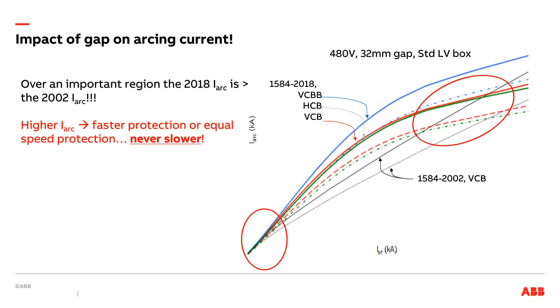I'm not addressing that here. I'm trying to address your more typical industrial commercial systems where your gear is rated 65 kA or below, and you're dealing with those more reasonable typical currents. In that IBF range, arcing current typically in the new study will be higher than in the old study. That's a good thing. Makes it easier to detect.